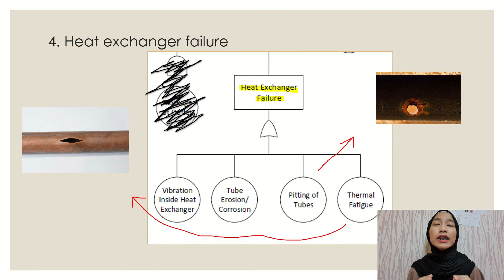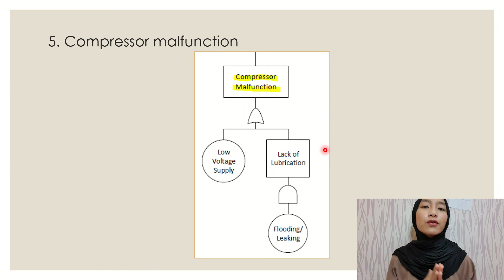Here goes why. We are aware that if the voltage supplied to the compressor is low, it will automatically result in compressor failure. Okay, next, low lubricant level can also give rise to a number of serious issues regarding compressor failure. Just as the compressor is the heart of our production system, the lubricant is the blood for the compressor.